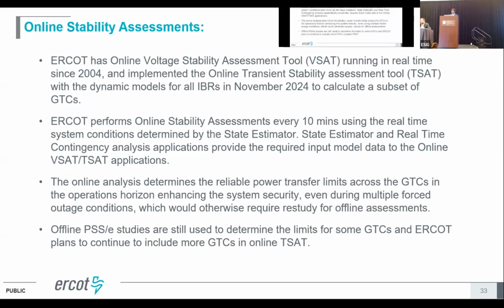And then once the limit is calculated, our transmission constraint manager application gives the operator a visualization of the percentage overload, how close we are, and how much margin we have on the GTC. Then when they activate the constraint in the security constrained economic dispatch, it will redispatch the generation to maintain the flow. The redispatch could be curtailing the generation behind the GTC, and then probably ramping up the other units outside the GTC area.